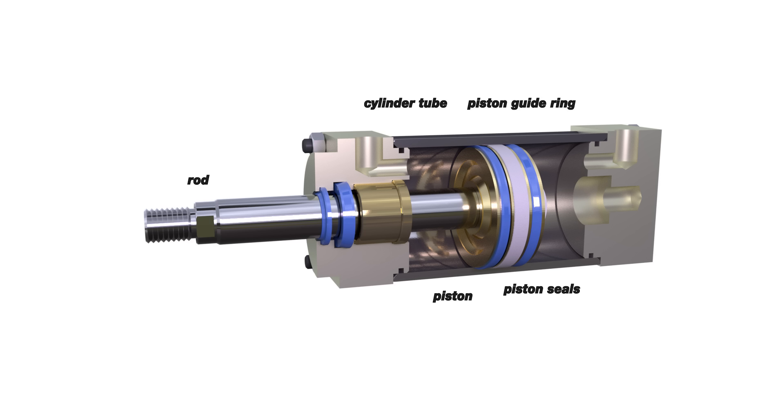To make the pneumatic cylinder air tight, you should install the front and end caps by placing O-ring seals at the joints between the cylinder barrel and caps. These caps have holes for supplying compressed air. The front cap has a seal to prevent air from flowing along the surface of the rod and a wiper seal to prevent dust from entering the pneumatic cylinder cavity.